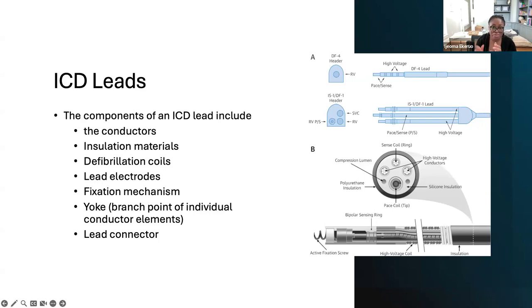There's a yoke sometimes - this is really just with the DF1 leads, where you have a separation of the pacing components and the defibrillation components. A DF4 lead, which kind of brings all of that together, does not have a yoke. The yoke used to be considered a point of weakness in the lead, and that's the reason why we have the DF4 leads now. And then, of course, the lead connector, which basically goes into the header.